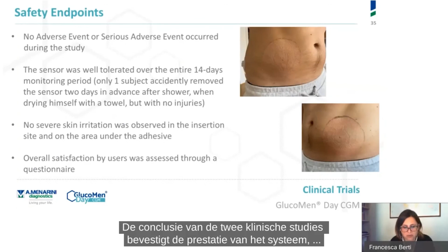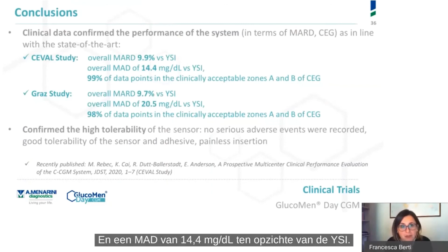In conclusion, the clinical data from the two studies confirmed that the performance of the system in terms of MARD and CEG are in line with the state of the art. For the CEVAL study, we obtained an overall MARD of 9.9% versus YSI, and an overall MAD of 14.4 milligram per deciliter. 99% of data points fell in the clinically acceptable zones A and B of the consensus error grid. For the Graz study, an overall MARD of 9.7% versus YSI was obtained, and an overall MAD of 20.5 milligram per deciliter. 98% of data points fell in the clinically acceptable zones A and B of the consensus error grid.